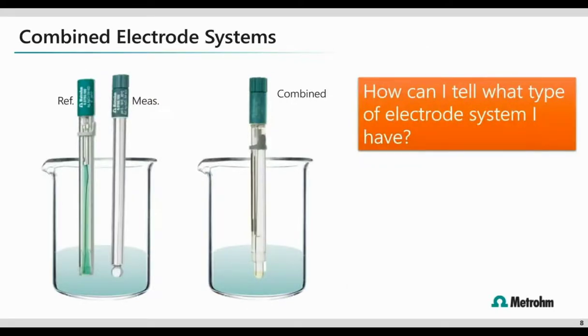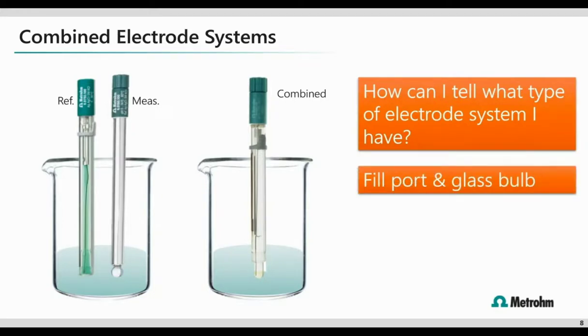More commonly today, we see combined electrode systems. And this is really because it's more convenient to have both components built into a single sensor. It takes up a lot less space in our sample and is less dependent on sample homogenization and simply reduces the surface area exposed to the sample. This means we basically have less to worry about in regards to cross-contamination as we move from sample to sample. So after this session, you may go back into the lab and wonder, what type of electrode system do I have? Simply look to see if you have a glass bulb and a fill port. Those are the easiest telltale signs of a combination electrode system.